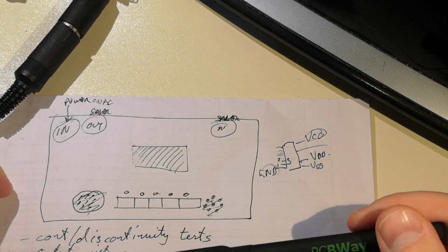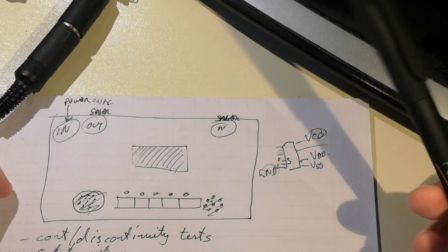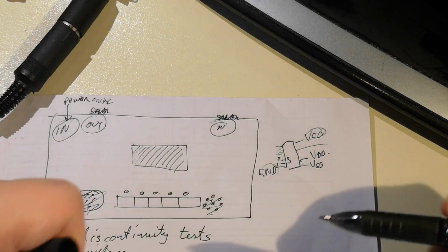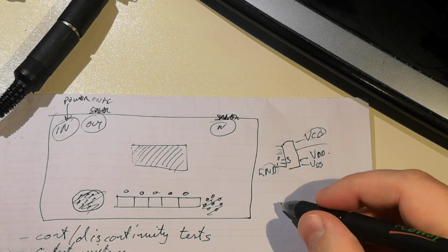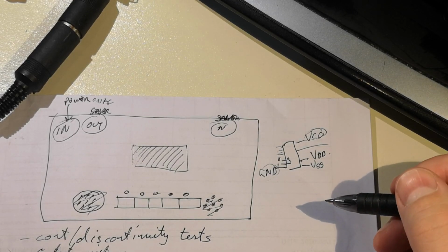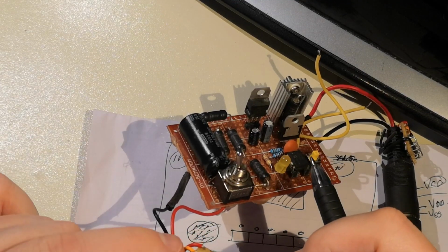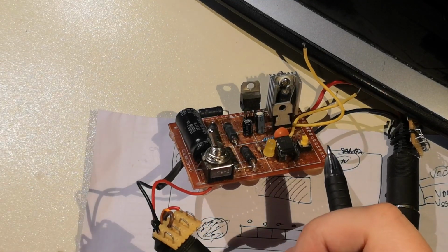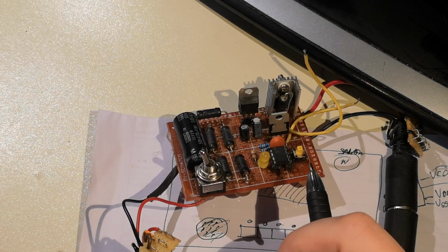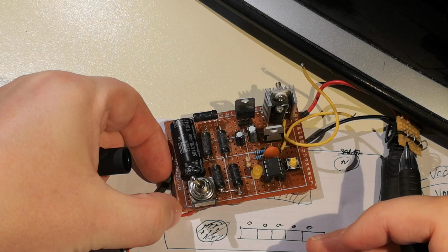You also need to check contact resistance. We need some millivolt measurements. When you test low resistance, it's difficult. So what I did in this one is that these wires you see here are actually connected directly onto the contact points. So I'm not measuring out here like normally I would do.